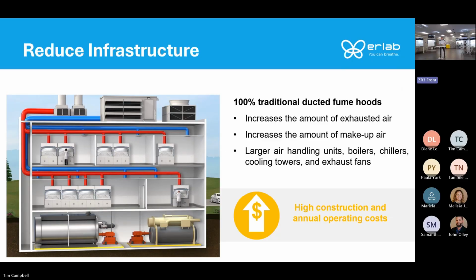And now if you're designing a lab from the beginning, this is just an example. This is, say, a traditional lab space that was all ducted. About 5 different labs there, a couple with a single hood, a couple with 2 hoods, and one with 4 hoods. So if you look through there, you see the size of the ductwork, which is the red and the blue. On the roof, you see the air handling units, the exhaust fans, and the cooling tower. In the basement, you see the size of the chiller, the cooler, and the boiler.